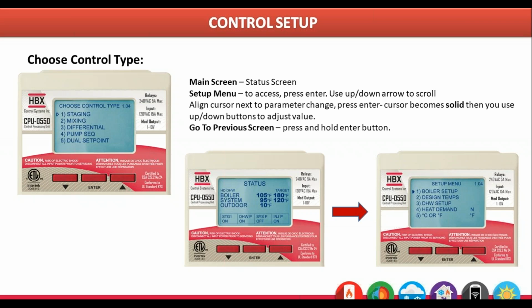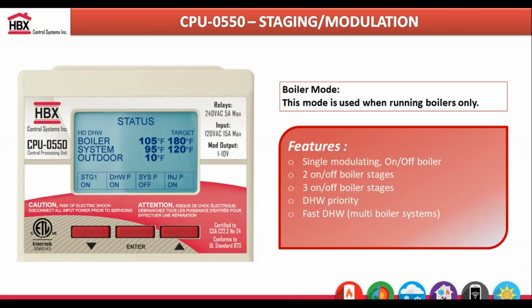It's simply going to ask you questions about your setup. You just have to enter those parameters into the controller and adjust how you want to stage your boilers based off time. If you want to rotate your boilers based off hours or run time, you can do that as well. You also have domestic hot water capabilities for domestic hot priorities when you are implementing that within the controller.